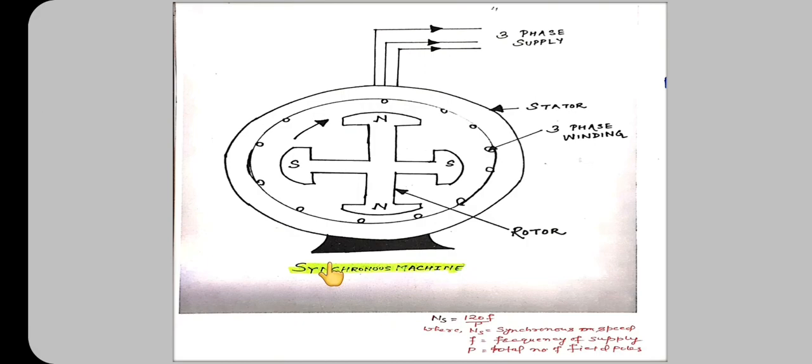The advantages of stationary armature and revolving field systems are as follows. First, it is easier to insulate the armature winding for very high voltage because insulation of a stationary armature is not subjected to mechanical stress due to centrifugal action and high speed, and more space is available on the stator for providing more insulation as the stator is outside the rotor.